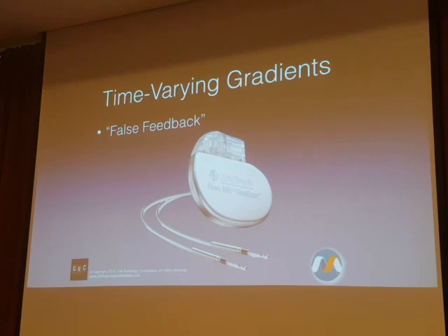Pediatric patients have an advantage over us adults by virtue of the fact that they are smaller. The gradient amplitudes, and we'll discuss this more in just a minute, are at their greatest near the periphery of the bore. At the center, ironically where the anatomy that you're trying to image is, the gradients are close to their minimum. It's the peripheral tissues that experience the greatest gradient amplitude shifts, and so it's in those tissues where peripheral nerve stimulation is most likely.